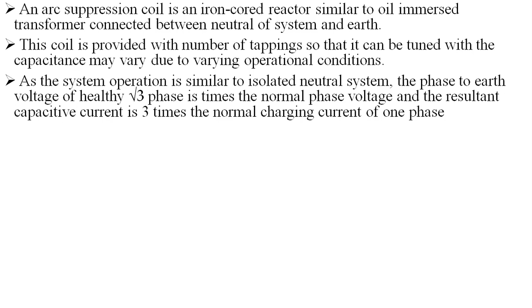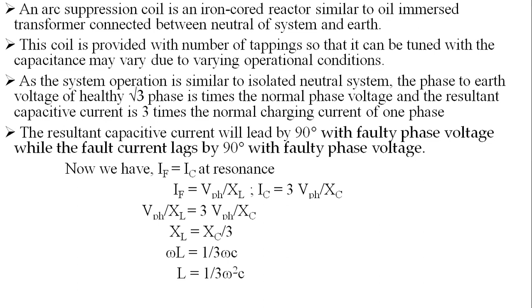So now we have IF equal to IC at resonance. That means the fault current will be equal to the capacitor current, and the fault current is nothing but the phase voltage per reactance. IC will be equal to 3 times the phase voltage per capacitive reactance. Equating those two, V phase by XL is our fault current, and 3 into V phase by XC is our capacitive current. Equating these two at resonance, we get the relation that the line reactance XL will be equal to XC by 3. We know the inductive reactance XL equals omega L, whereas XC equals 1 by omega C. Hence omega L equals 1 by 3 omega C, thereby L equals 1 by 3 omega square C.